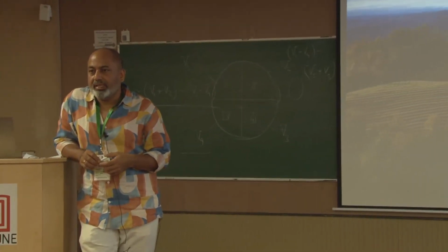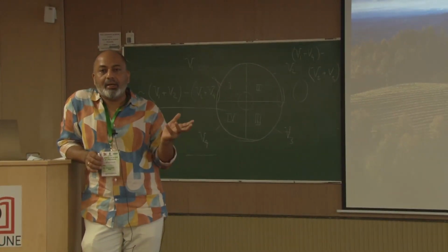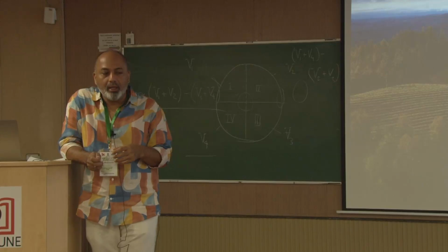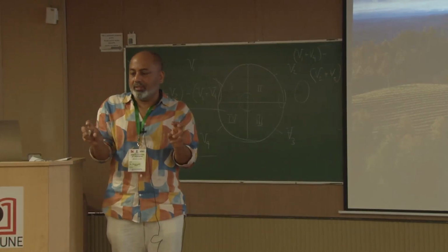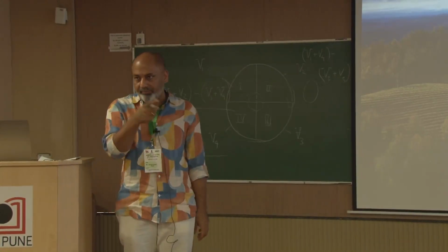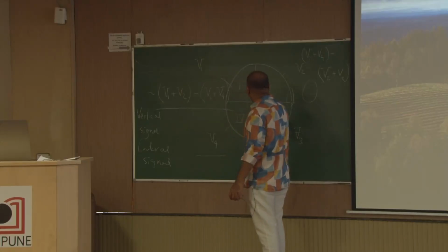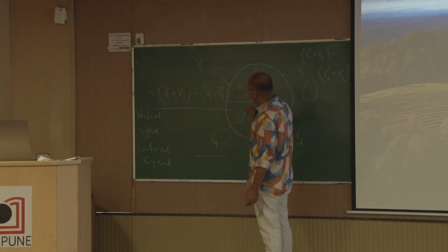Laser beam profiling. Good question. Many times the laser comes with modes. This is where the problem comes: the side modes will fall and the central one will be there. Sometimes the mode is elliptical. So if this goes back here, it will be elliptical, and if it is at an angle, there are all kinds of problems.